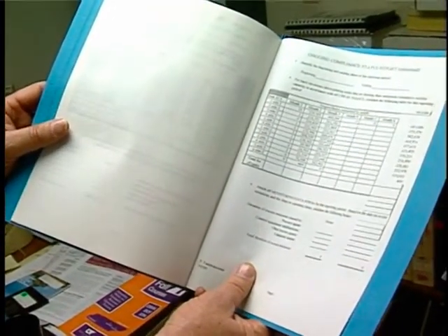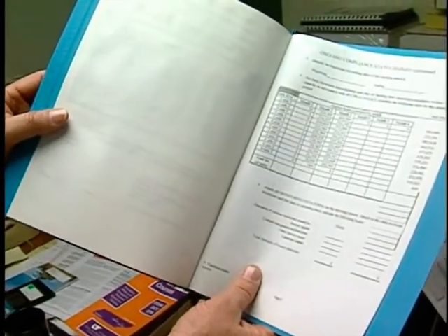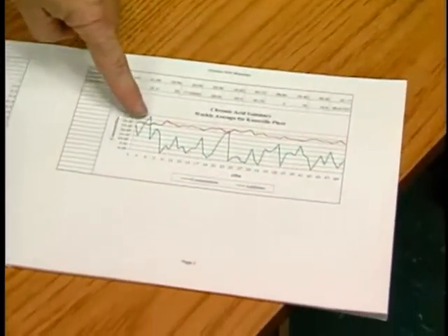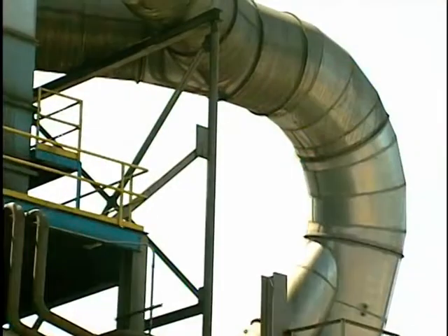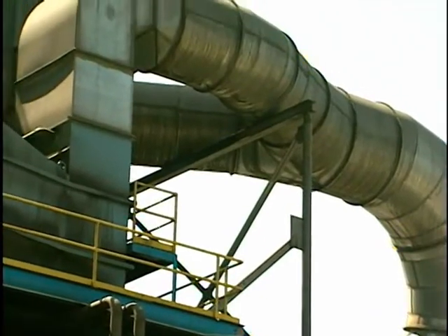Finally, component failure records should be evaluated. An increase from the normal failure rate indicates that the source should carefully evaluate the cause and correct the problem before equipment damage and excessive emissions occur.